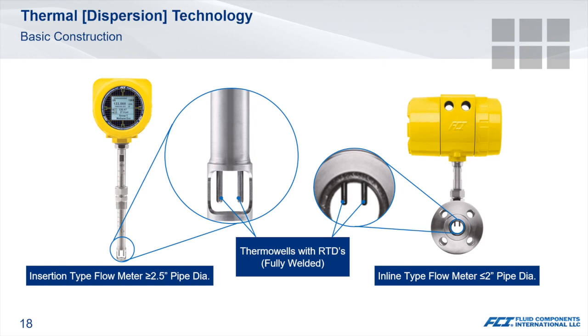Thermal meters are commonly categorized as inline or insertion. In either case, we are dealing with fully welded sensors consisting of 2 sheathed RTDs. There are no moving parts, so these sensors are not prone to wear or leakage. There are no small ports or orifices that can become fouled to the point of making the instruments non-functional.